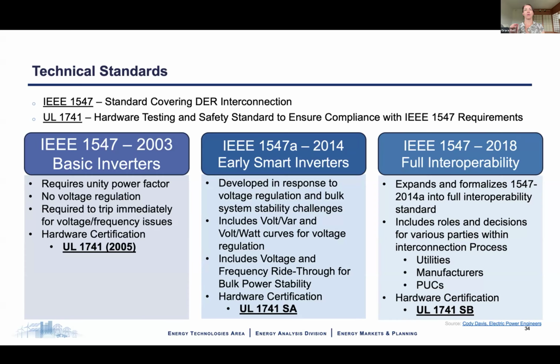The latest standard being what we call IEEE 1547-2018. It's kind of a mouthful, but it focuses on how inverters can provide grid service functions like voltage and frequency support and have communications functionality with the utility. This is really important for having visibility into what DERs are doing and to minimizing possible negative grid impacts. And then you can maximize the value of these resources on the system too.